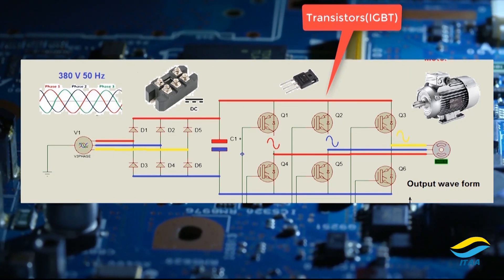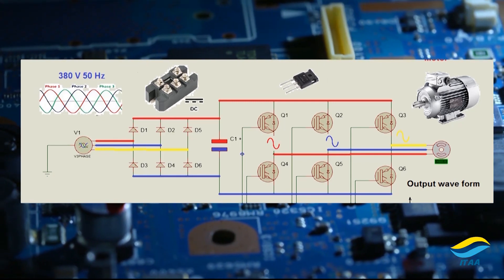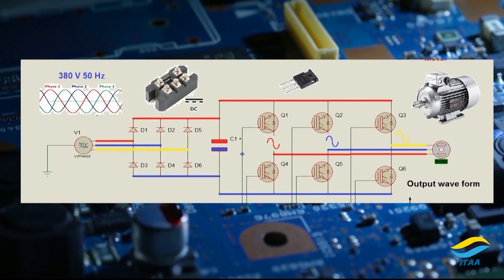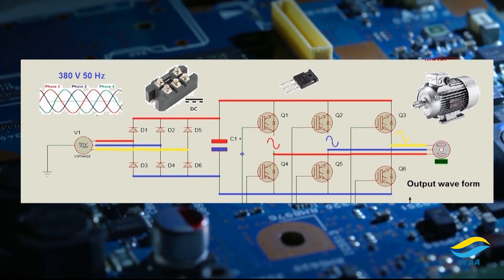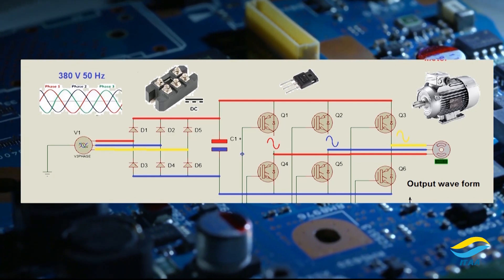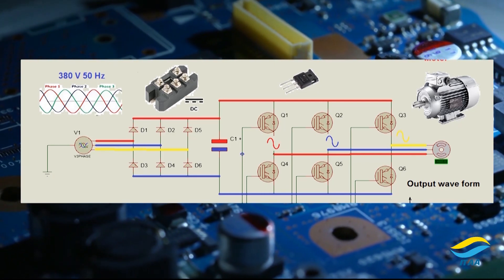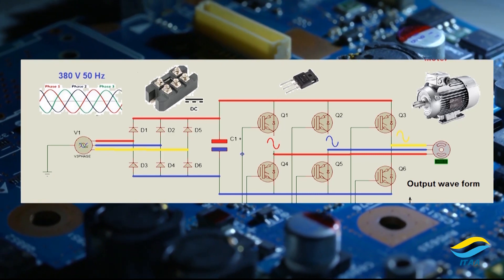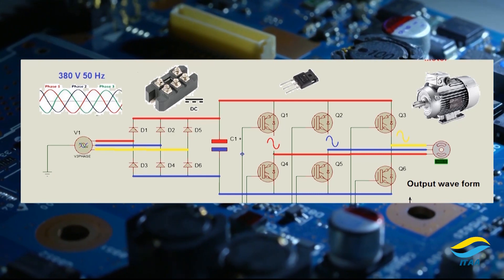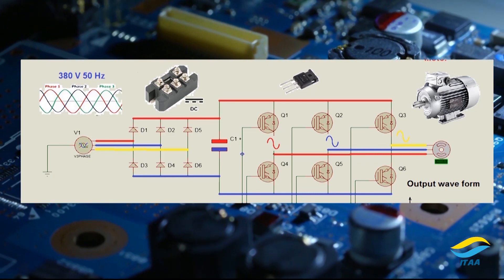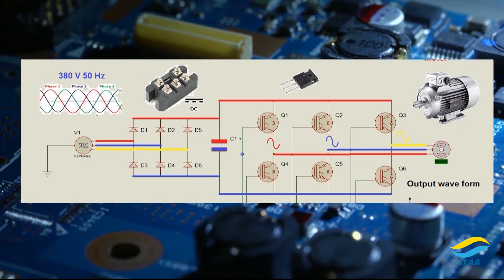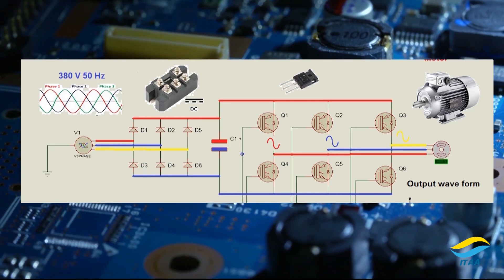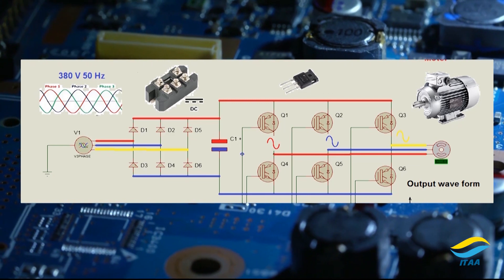By using these switches, we are actually controlling the frequency of the motor, which in turn controls the speed of the motor. As you know from the basics of physics, frequency is directly proportional to speed. If frequency goes high, speed will go high; if frequency goes down, speed will go down. By switching these IGBTs, we can create any frequency we like, and that frequency will vary the speed accordingly.